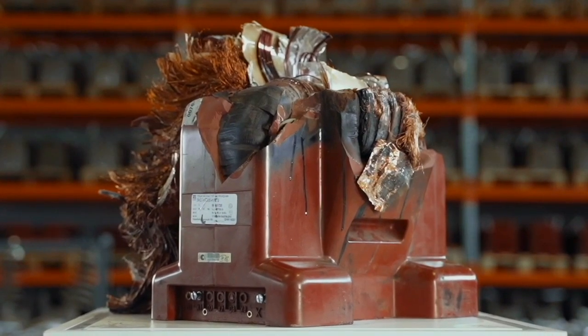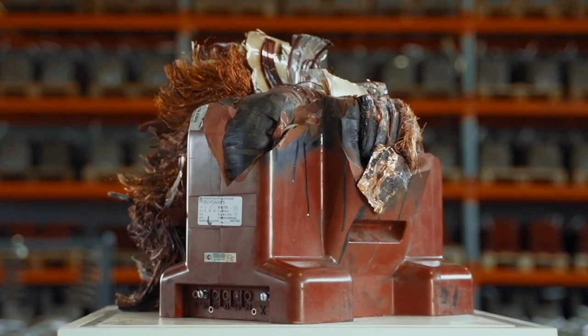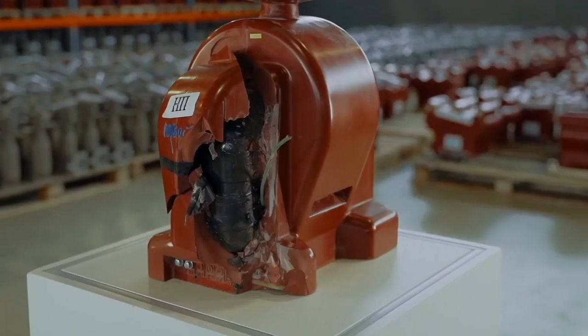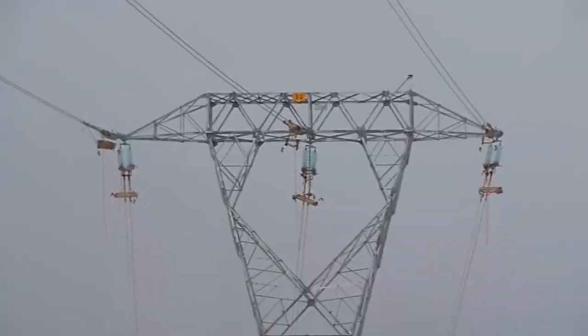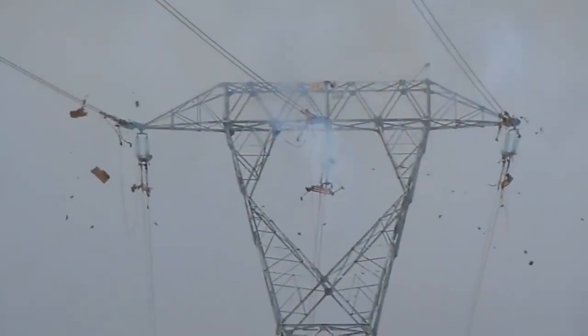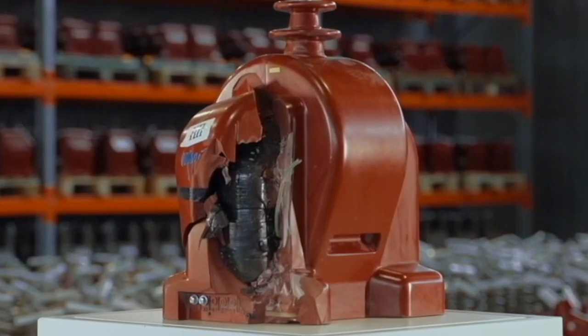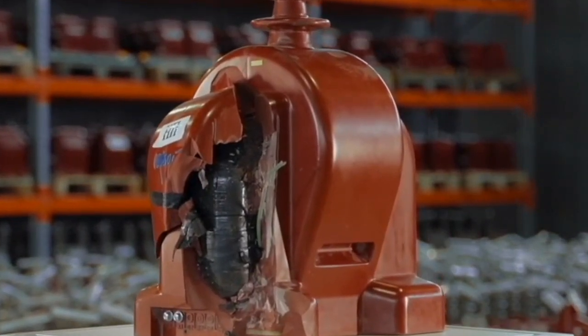Single-phase transformers are massively damaged around the world in isolated neutral networks due to the appearance of the ferroresonance effect. The processes that occur during ferroresonance drive the voltage transformer into saturation mode, in which ultra-high currents arise that overheat the transformer, which ultimately ends in the failure of the equipment. This type of damage is widespread. Thousands of transformers around the world are damaged, especially in isolated neutral networks.